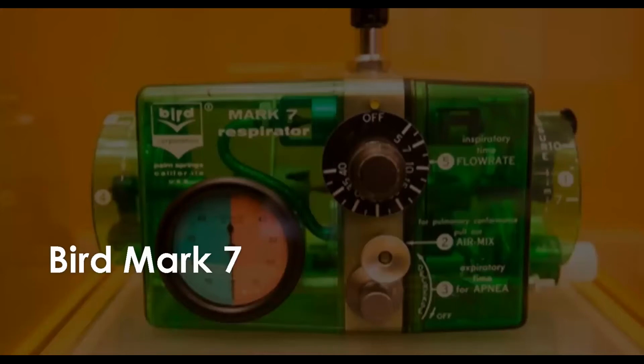Since then, however, there has been a lot of progress with the design of ventilators, including better control facilitated by computers. Moreover, research and studies have helped physicians to calculate the optimum level of oxygen that should be delivered into patients' lungs in each breath. For example, a study in 2000 showed that the tidal volume, which is the volume of air that should be forced into the lungs during a particular breath, was shown to be more effective when lower than the volume that machines had been delivering at the time. And so this helped increase the survival rates of patients relying on the ventilator.